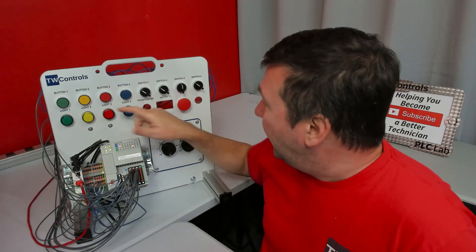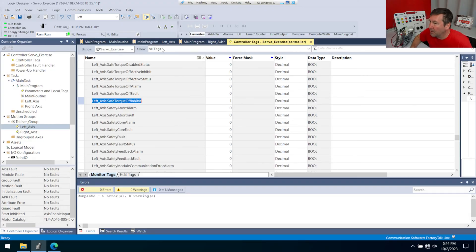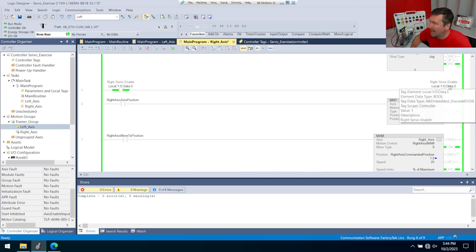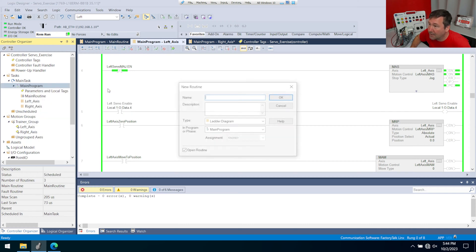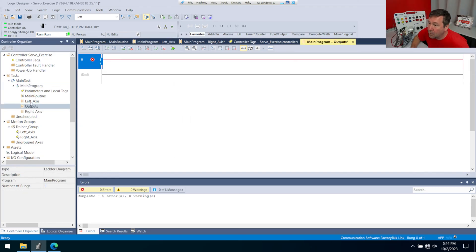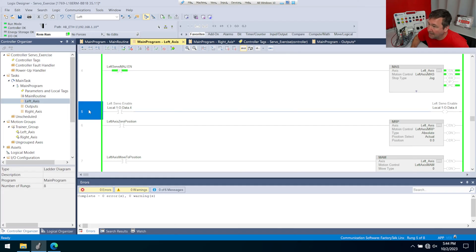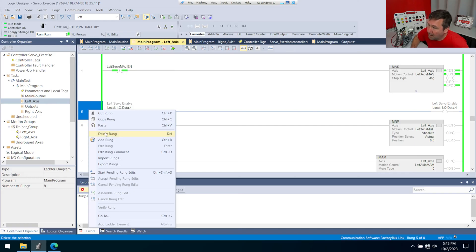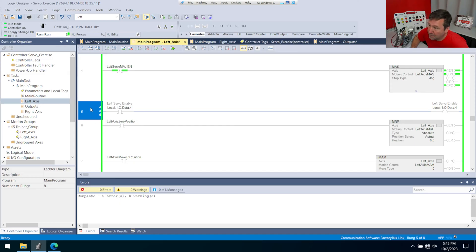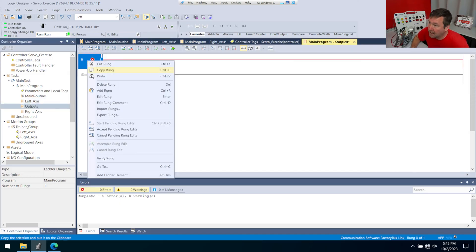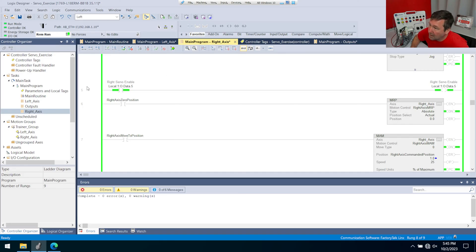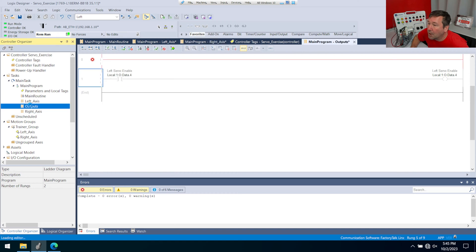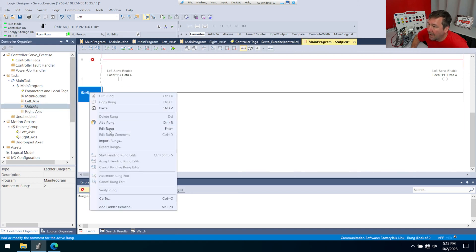Let's make the safe torque off turn on the red light, and let's organize our code a little bit more. Right now we have the right axis output over here and the left axis output over here. Let's make a subroutine just for our outputs. Right-click the main program, add new routine, and call it outputs. Then go into the left axis, right-click the enable rung, and cut that rung — notice it flags it for deletion. Go over to outputs, right-click, and paste it. Then go into the right axis, right-click the enable rung, cut it, go to outputs, and paste it there as well.